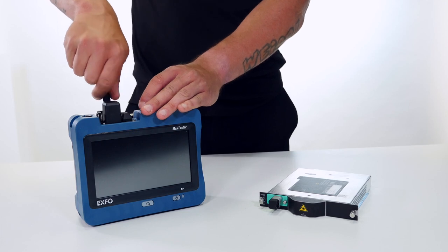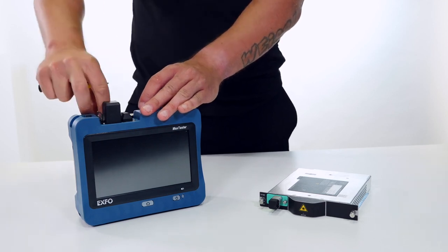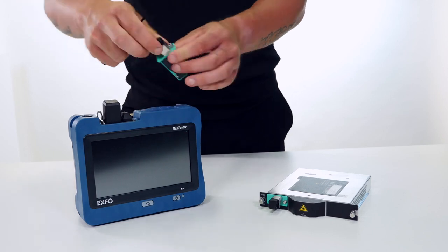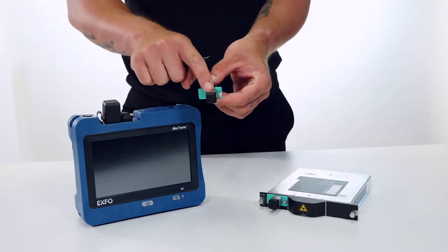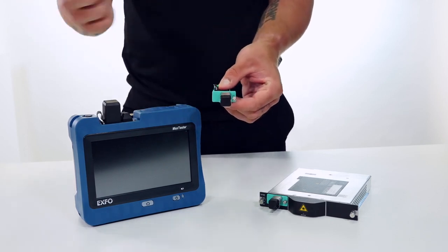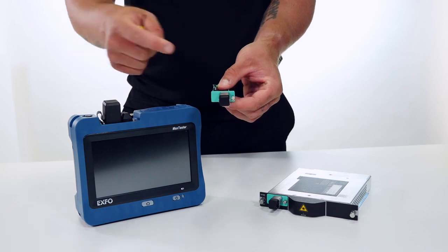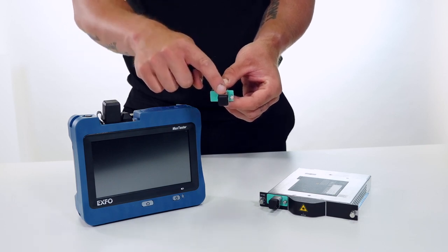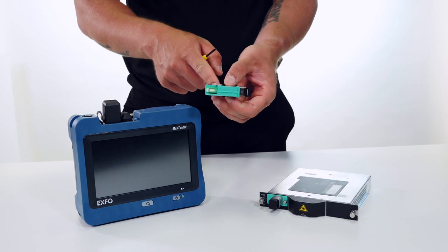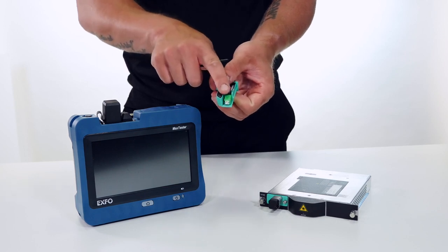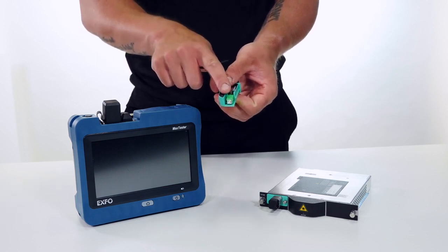The reasons why we might want to change our swap out connector is if the external connector has become damaged from overuse, from multiple connections and disconnections. So we can change the connector itself, and it's going to minimize the number of connections on the internal connector, which is where the calibration is done.